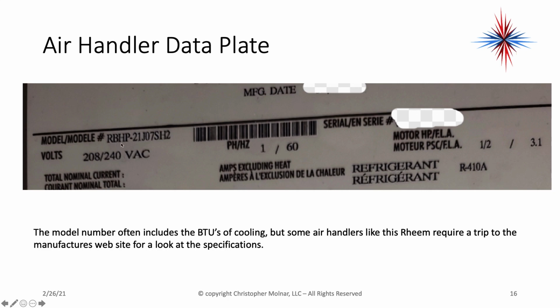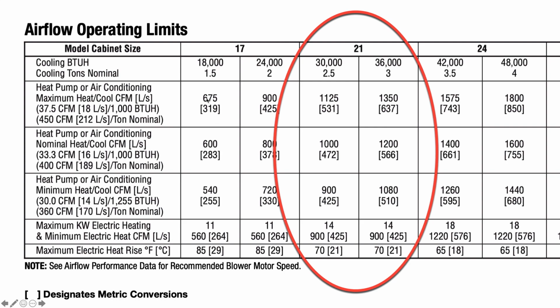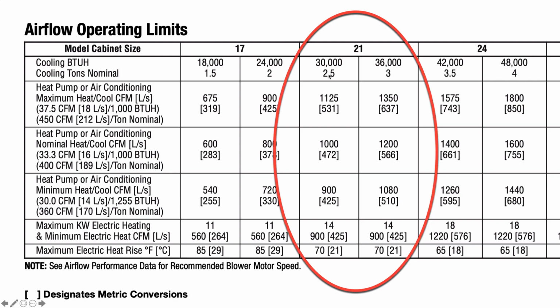Because this model number, RBHP 21, just tells me the cabinet designation. It doesn't tell me the BTUs of cooling or the tons of cooling. Some air handlers will have an 18, 24, 36, or 30 in here, and that's actually telling you the tonnage or the BTUs of the system. Now, if I go to the Rheem website and pull up the specifications for this model number, I'm going to find a column for 21.